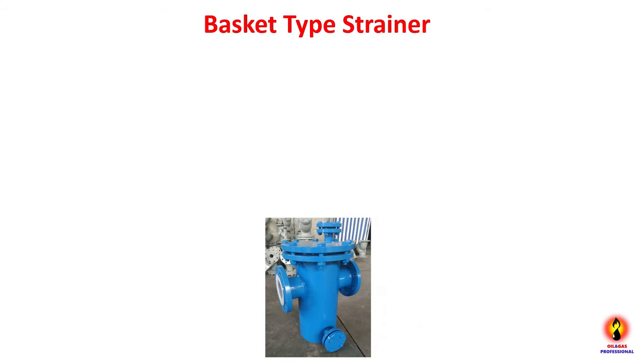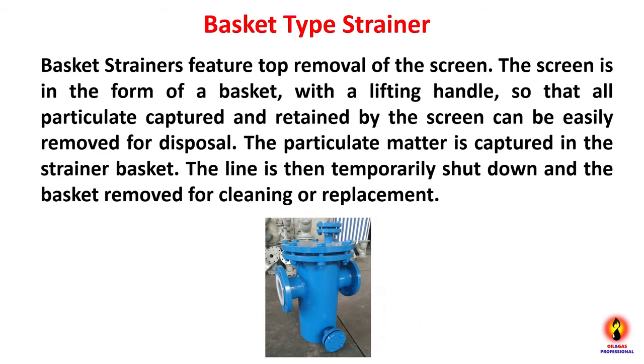Basket type strainer features top removal of the screen. The screen is in the form of a basket with a lifting handle, so that all particulate captured by the screen can be easily removed for disposal. The particulate matter is captured in the strainer basket; the line is then temporarily shut down and the basket removed for cleaning or replacement.